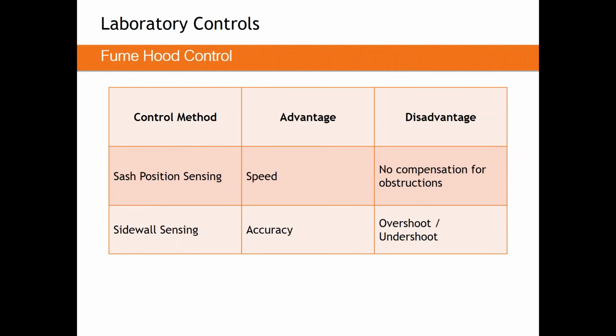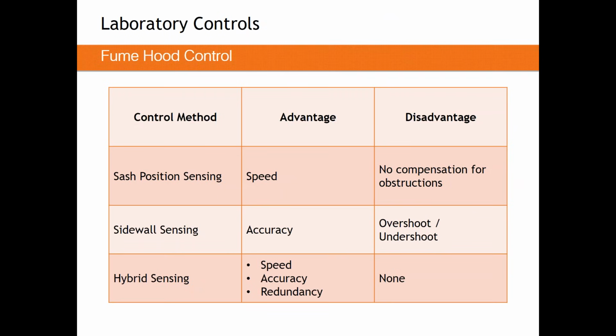Sidewall sensing, on the other hand, is very accurate. Though because it is a control loop, it is tunable, it can overshoot and undershoot a little bit, and it's a little bit slower. What we like to do is called hybrid sensing. So especially for a combination sash, what we think we should do is use both sensors for what they're best at. Sash sensors are quick, so whenever the sash is moving vertically, we would engage our sash position sensor. This gives us a really good first guess. As soon as the sash stops moving, we would give control over to the sidewall sensor, meaning get us close, but then give control to the more accurate device to tweak and tune us right into the place we actually want to be. This is now also a redundant system.